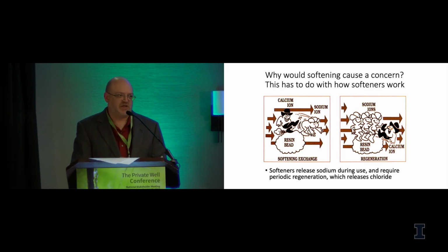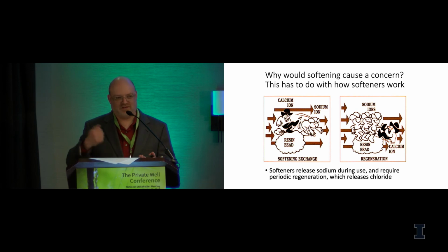To understand this conversation, I need to give you a little bit of information about how softeners work. This slide shows you a representation of the resin beads that are inside the softener tank. When those beads are fully regenerated, they have sodium, so they're attached to a sodium. And the calcium comes in, the big bully calcium guy, and the resin bead actually has more affinity for the calcium and the magnesium than it does for the sodium. So the calcium comes in, kicks the sodium off, the sodium's discharged. Eventually the capacity of this bed to absorb hardness is used up, so we need to regenerate.